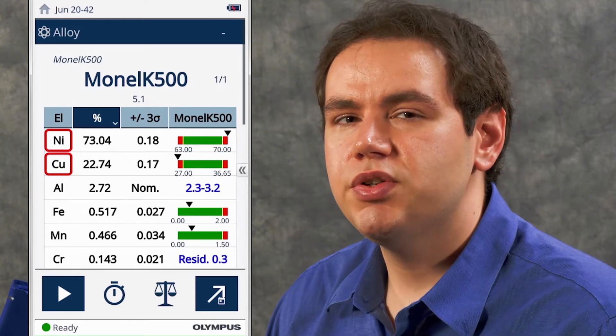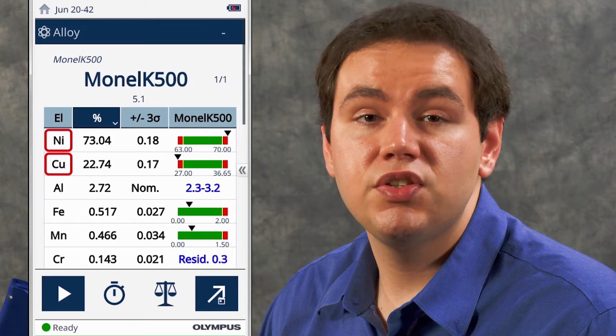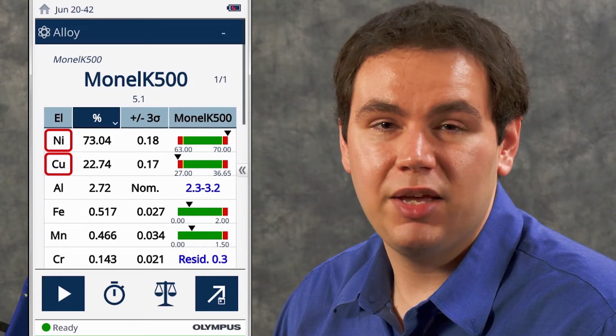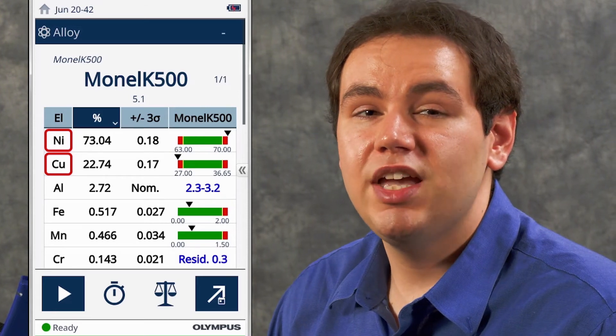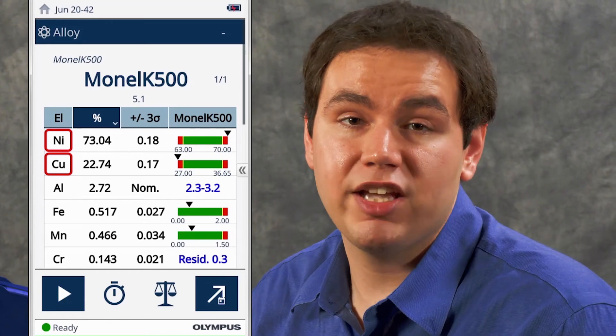You may also notice during testing that initially a match is shown, but then as the test finishes, no match appears. This occurs because as the precision increases over time and the amount outside of the specification increases, we penalize the match number more, and that results in no match being displayed. I hope explaining what no match means has been useful for your alloy testing. Thank you for watching.